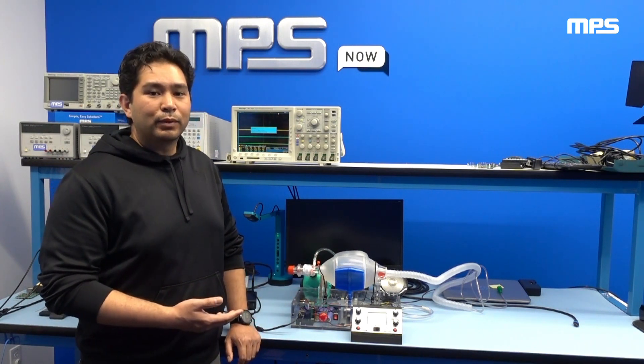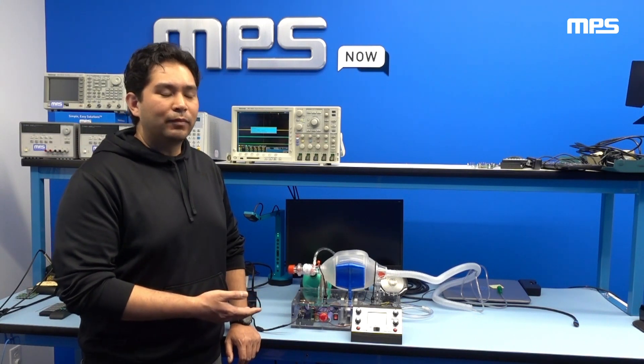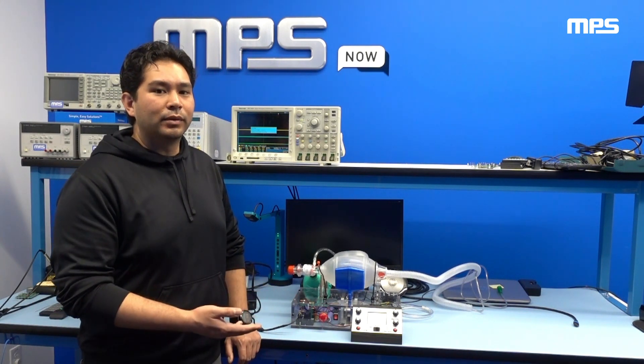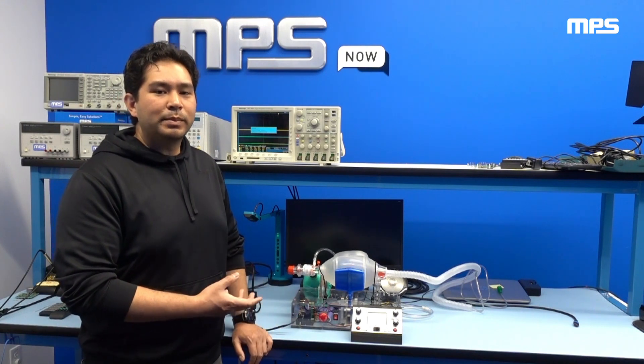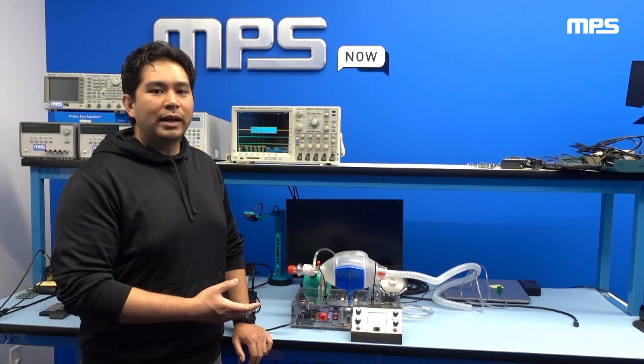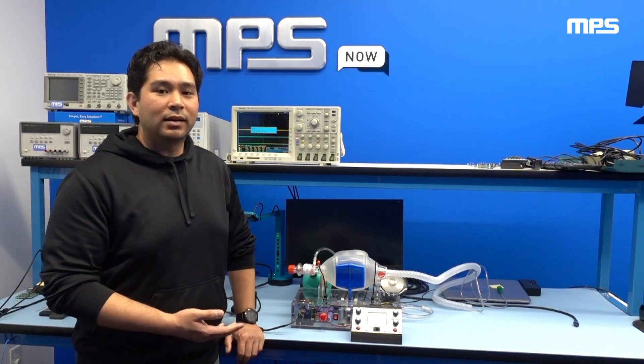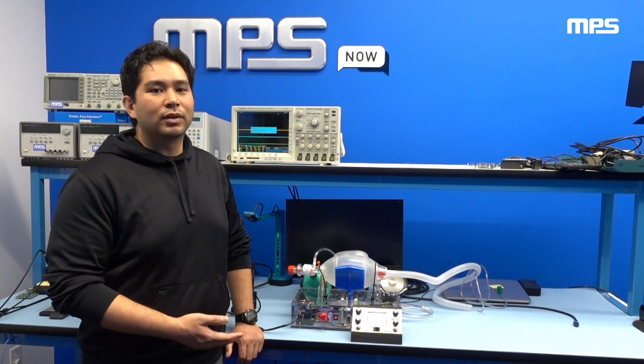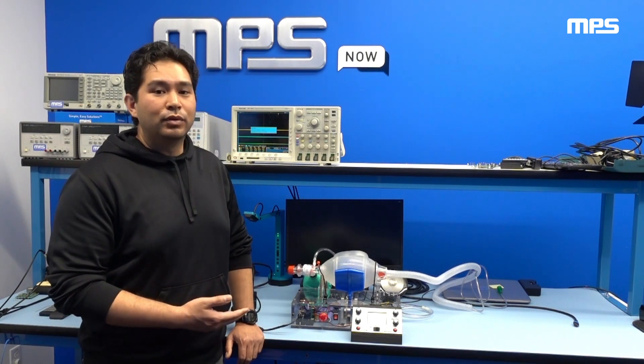With that information, we plan to upgrade our motor to a larger NEMA 17 smart motor — from the 38-watt motor we started with up to about an 80-watt motor — as well as modify our squeeze pad geometry to enable more volume to be delivered. We'd like to thank Dr. Miller again for that great opportunity, as it was invaluable for us to learn and understand how we can improve our device.